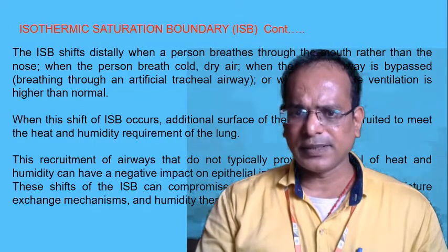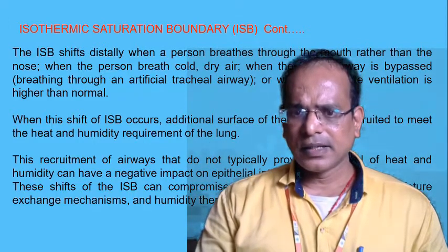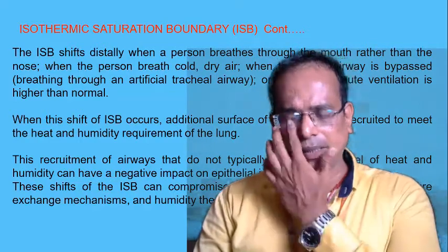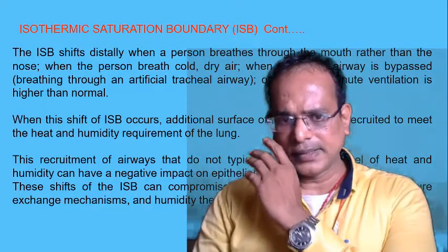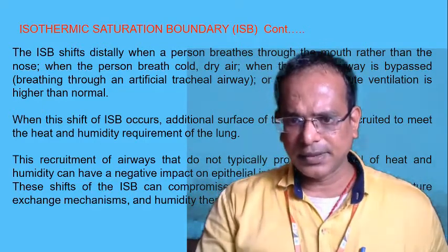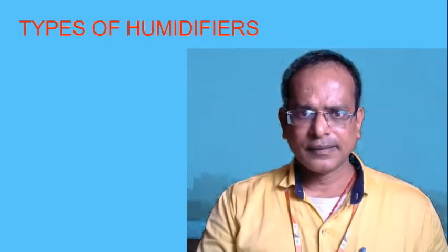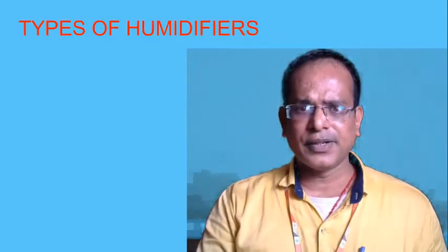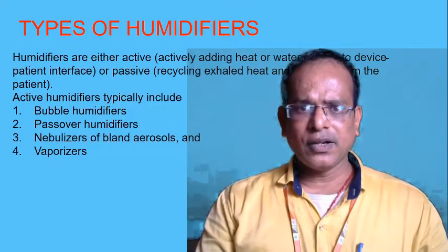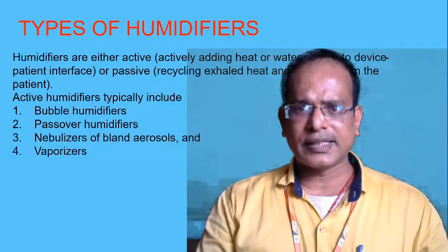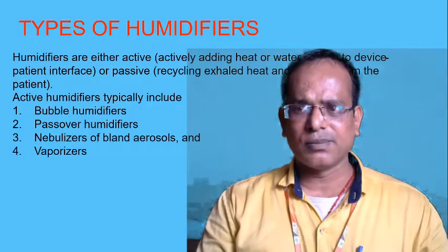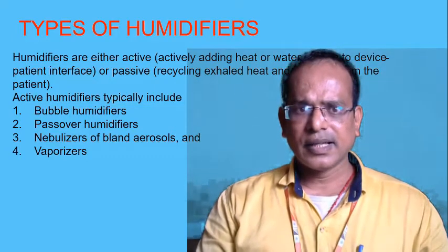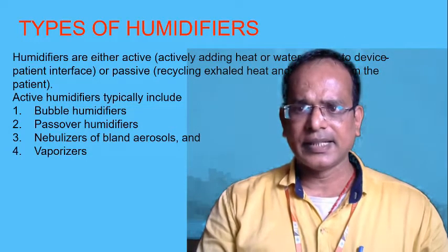This shift can compromise the body, the normal heat. The moisture exchange mechanism and humidity therapy is indicated. The types of humidifier: humidifiers are either active, that is actively adding heat or water, or both to the device patient interface, or passive, recycling the exhaled heat and humidity from the patients.